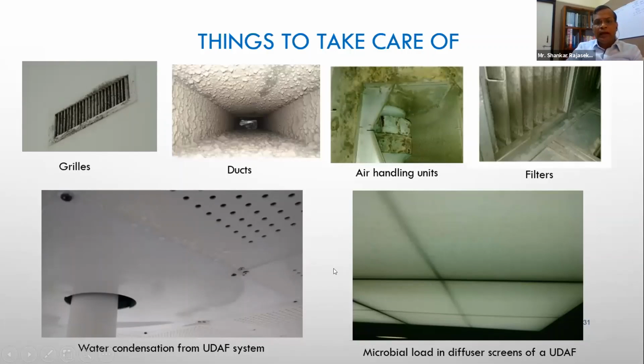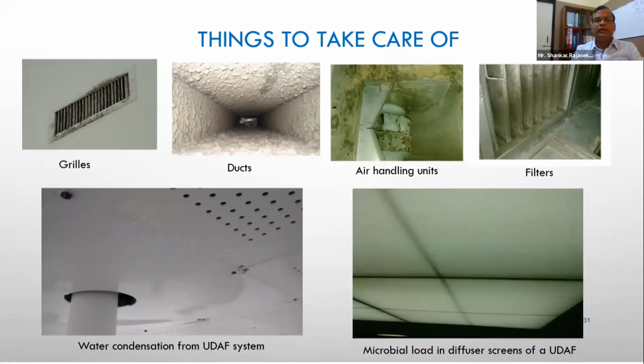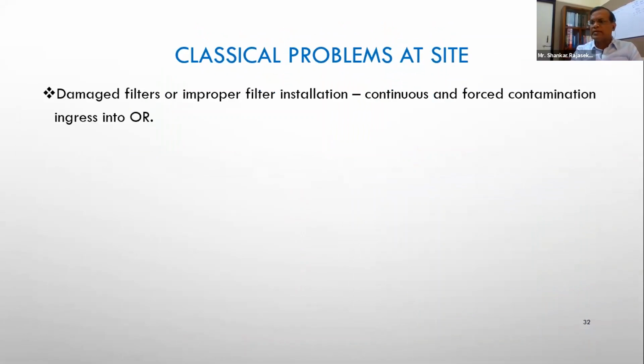There have also been several cases where we have seen high microbial load in the diffuser screen of the unidirectional airflow system. These things are really wrong, in the sense that the equipment which is supposed to be providing the benefits of clean air itself becomes the culprit. So as engineers, we need to make sure such things don't happen. We'll discuss some of the classical problems that we experience at site.